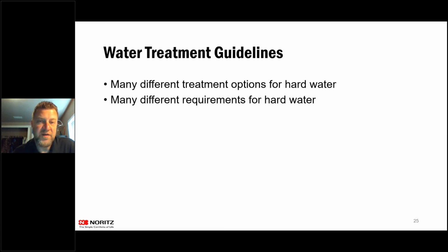With our units, we actually have a specific flush technique that needs to be done to the unit, where you put a connector together that puts the unit into flush mode, which records the date and how many times that unit's been flushed. So if you were to call our tech support because something was going wrong with the unit, say the heat exchanger was leaking, we could look at it and see how many times it's been flushed and how many days it's been since the last flush.